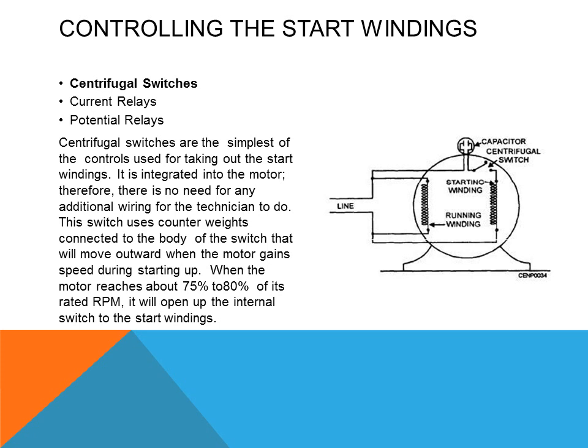A centrifugal switch is the simplest type — it uses a mechanical action with counterweights that use centrifugal force to move linkages inside the motor to open the start windings when the motor reaches full speed. As soon as the motor slows down or stops, the switch will close again.